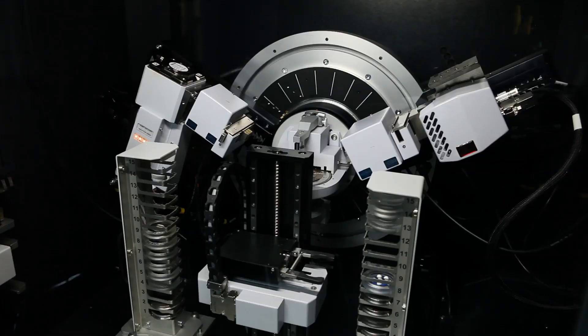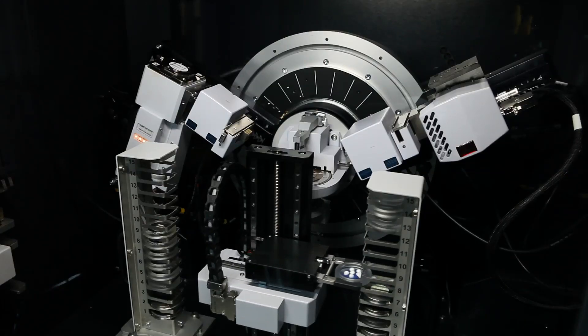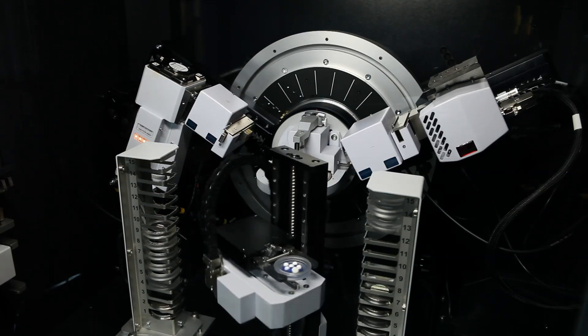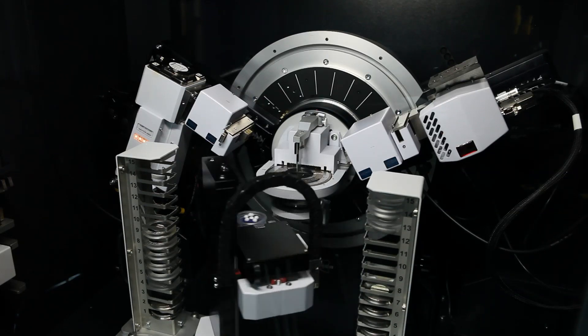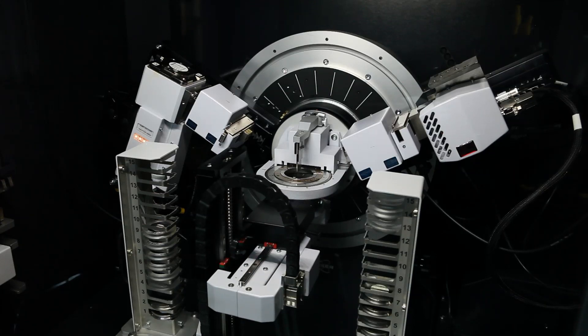This makes it very versatile and usable. So you can cover a wide range of applications without actually having to do any alignment on the system itself. And customers tend to love that because they want to cover a wide range of applications but they don't want to actually physically touch very expensive optics or have other people touch it. So I can run many samples overnight or I can even run very complicated scans on the same sample, and I can extract all the benefits of parallel beam geometry and divergent beam geometry.